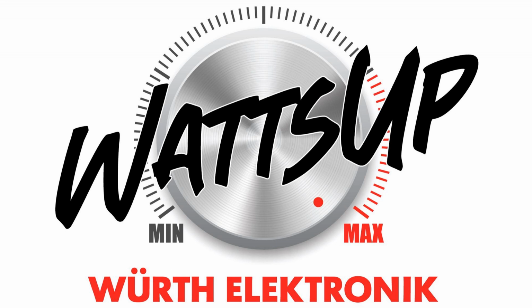Again, very often to see this kind of very wrong connection, that you come with a cable, you put the filter and you turn back again, and you have your capacitive and inductive coupling into the metal box enclosure. Especially industrial electrical guys, they just take the easy way, just connect to the wall in the very correct way, in the shortest way, but then they route the cable again close by the entrance, and again it's a big problem. So try to do in the construction that you're not crossing or coming close to this area where you have the filtering effectivity, because else it won't work so well.